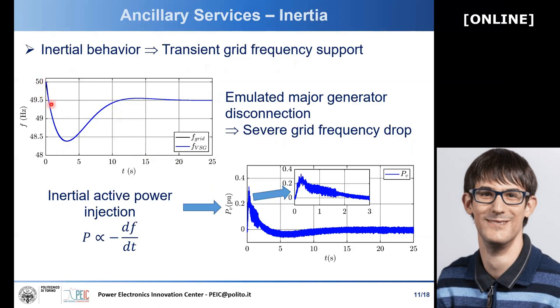Here you can see what the inertial effect means with experimental results. This is a test we ran in our lab where we emulated a frequency event with a grid emulator — for example, this can happen when a very large generating plant trips. The VSG response is proportional to the opposite of the frequency derivative, which is exactly the inertial effect, and as you can see, this is exactly what would happen with a real synchronous generator. The goal is to raise the frequency nadir and reduce the frequency derivative, thereby avoiding blackouts or unwanted triggering of frequency protection devices.